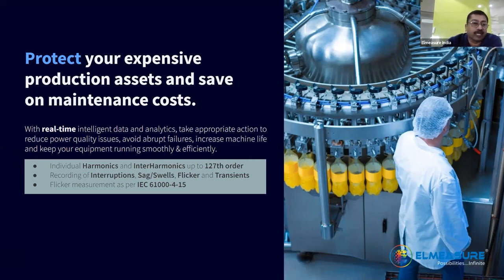So if you look at the standards, other than 61000-4-30 Edition 3, which comes under the Class A category, then for flicker, and for harmonics, you have specific standards, and the product meets those standards. That's very important, because only then can we say the product is actually meeting the requirement. So interharmonics, individual harmonics, interruptions, sags, swells, flicker, and 61000-4-15 for flicker measurement, this completely contributes to the power quality information we are talking about.